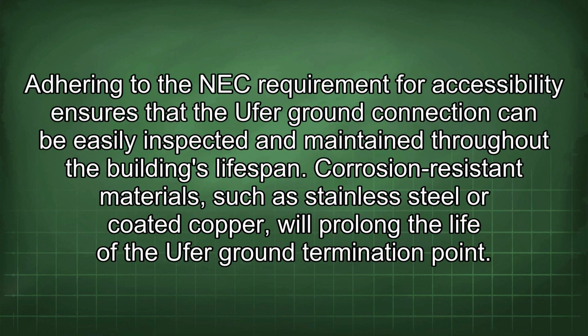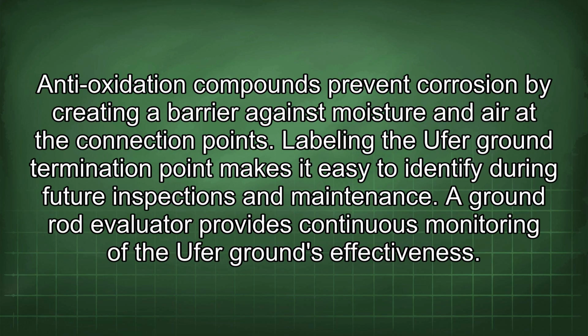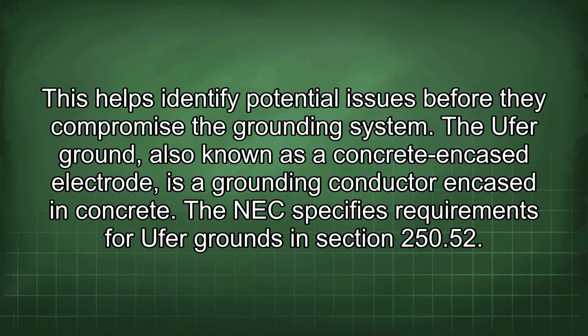Adhering to the NEC requirement for accessibility ensures that the Ufer ground connection can be easily inspected and maintained throughout the building's lifespan. Corrosion-resistant materials, such as stainless steel or coated copper, will prolong the life of the Ufer ground termination point. Anti-oxidation compounds prevent corrosion by creating a barrier against moisture and air at the connection points. Labeling the Ufer ground termination point makes it easy to identify during future inspections and maintenance. A ground rod evaluator provides continuous monitoring of the Ufer ground's effectiveness. This helps identify potential issues before they compromise the grounding system.